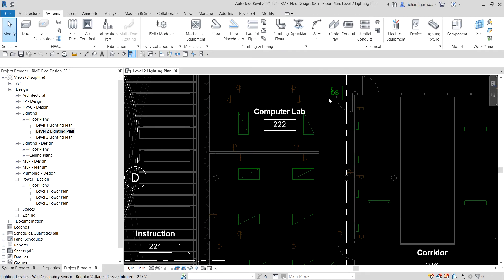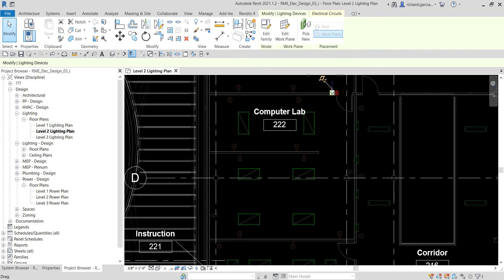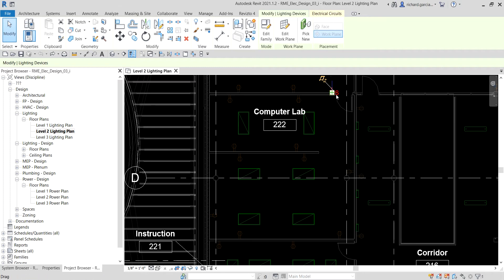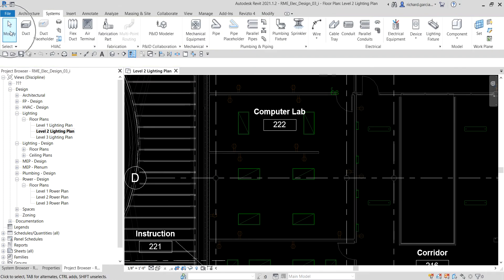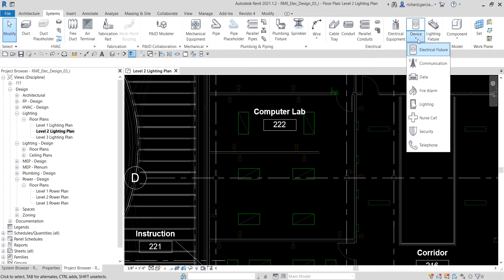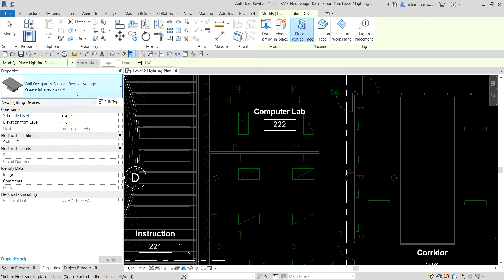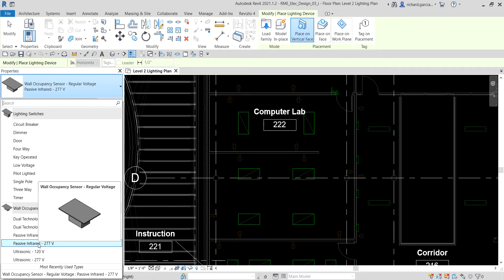To place these switches, we're going to insert another one of this type. You can select an existing one, right-click, and select 'Create Similar.' Or, if you want to know where to find the lighting switch, go to the Systems tab and then go to Lighting Device. Select 'Lighting,' check the properties — this is the 'Wall Occupancy Sensor, Regular Voltage, Passive Infrared, 277 Volts' that we are going to insert.